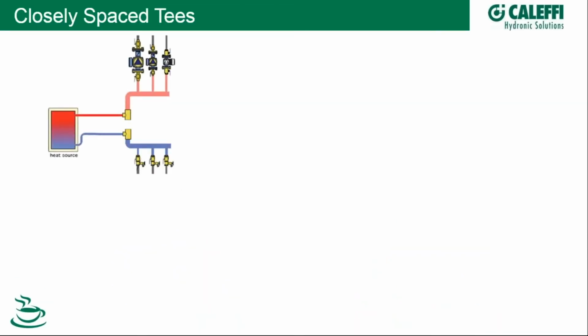So when we look at ways of reducing or eliminating pump conflict, and look at a very simple schematic here, we have a heat source. It could be a heat pump. It could be a condensing boiler, for example. And then we have 3 circulators sending heat up into our system and back. If we have a high resistance type header, as I show here, let's talk about what could happen in application. Let's say we have 3 circulators on here, and 2 of these circulators are on and pumping. Say these 2 right circulators are pumping 5 gallons per minute up into the system. That flow comes back around to the return header, completing its journey around to the boiler to be reheated, etc.